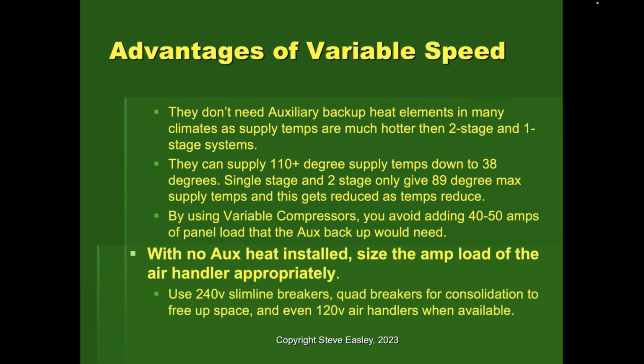In many of the climates, for example, the supply temps are much warmer than two-stage and single-speed systems. They can supply upwards of 110 degrees supply air temps. To my last person's question there, you can get upwards of 110 degrees supply air temperatures down to 38 degrees outside. Single-stage and two-stage systems might give you an 89-degree maximum temperature supply temps during that time. So just warn customers that traditional heat pump equipment is going to feel cooler coming out of the register.